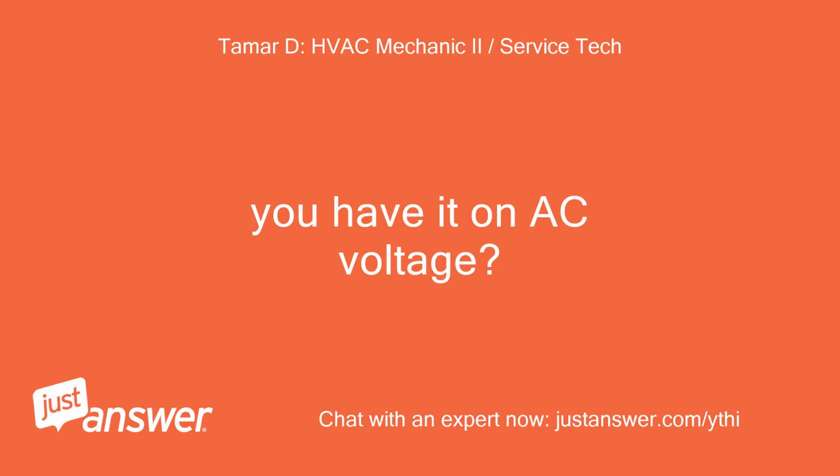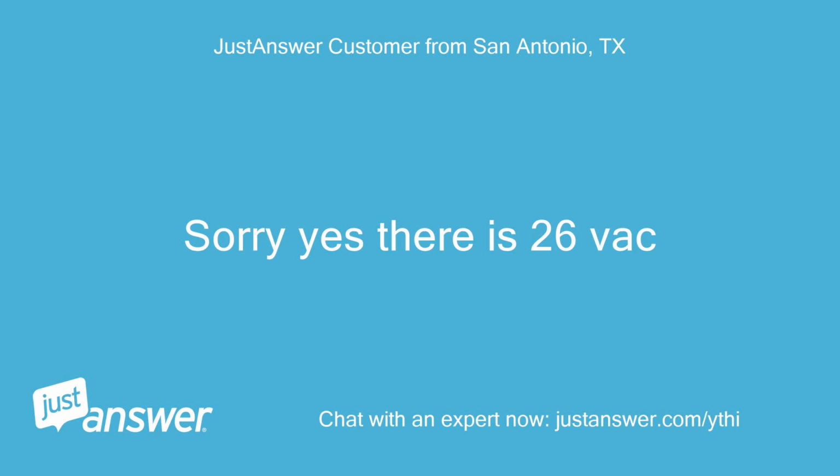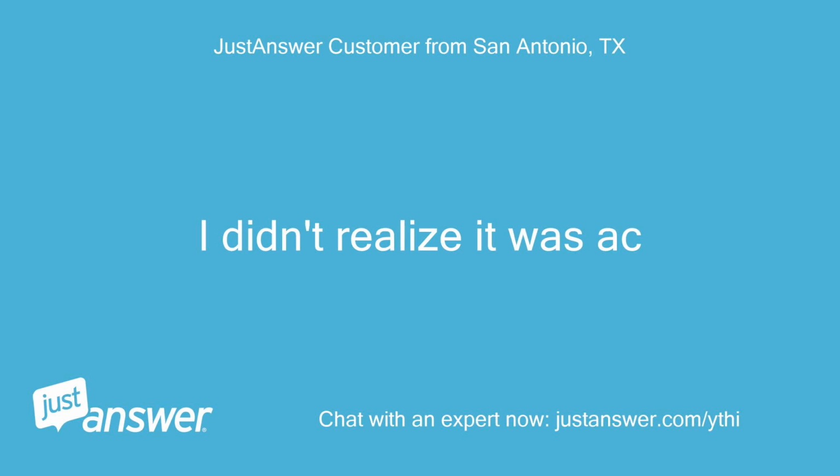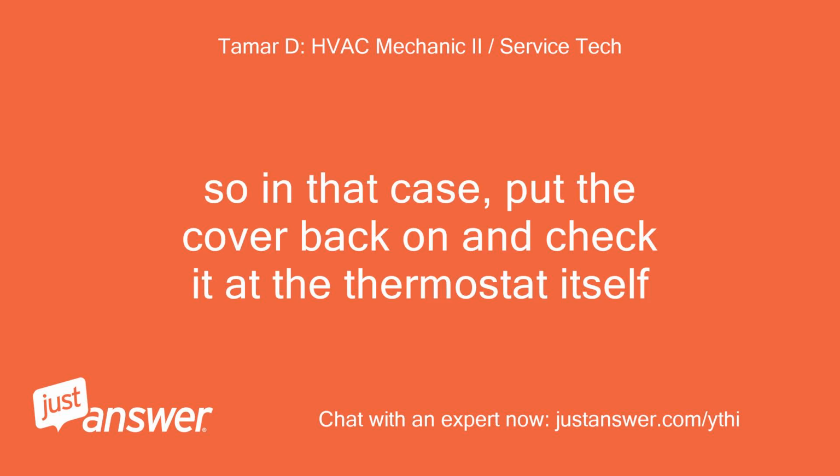You have it on AC voltage. If you do not have 24 volts AC on the R and C terminal of the board with door switch depressed, you need to check the low voltage fuse in the furnace. Sorry, yes, there is 26 VAC. I didn't realize it was AC. Okay. So in that case, put the cover back on and check it at the thermostat itself.